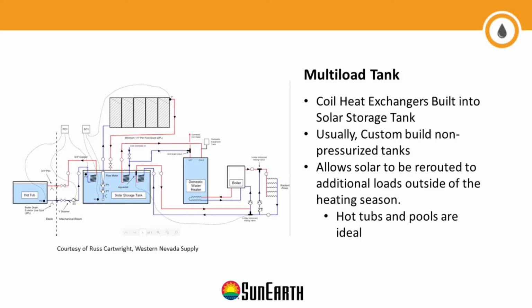This design doesn't use three-way valves. I was taught a long time ago that if you can, don't use a three-way valve. In solar thermal, systems are generally very passive, so if you use mechanical equipment, pumps tend to last a little longer than three-way valves. This one uses all pumps.